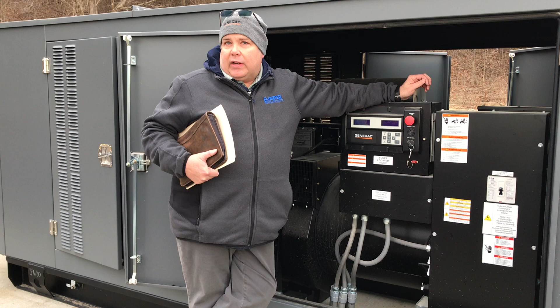We had problems at the high school where we were using a lot of oil because it wasn't running under load. Is there any other way around that besides running it with an external load for a period of time? That was natural gas and must be really unloaded. Other than probably when we started it up, we load banked it for 2 hours or whatever.